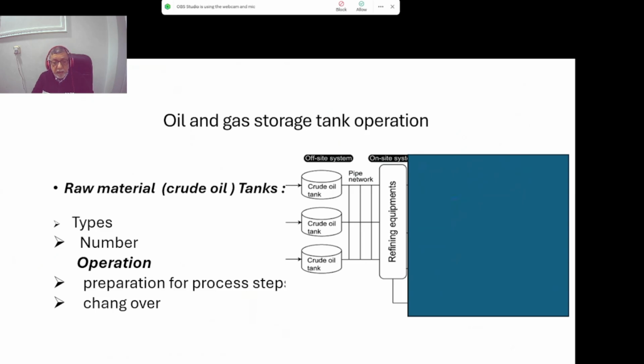The operation of tanks is a preparation for the process steps, meaning make the line up and then receive the product. This is after commissioning, meaning the tank is done and the testing is done for everything, and now it is handled by the operator, not by the commissioning team. So receive the product and monitor the level. Do not let the crude oil overfill, because this is a floating roof and it is dangerous to the terrace level.